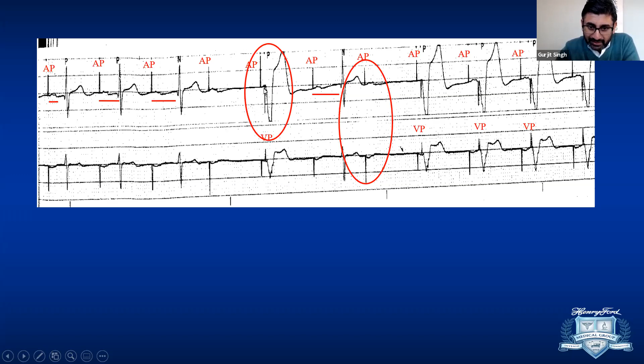Remember, we talked about last time, as Dr. Verdino also explained, this is a hallmark for a Medtronic pacemaker in MVP mode, that this ventricular pace signal comes after an AV delay of 80 milliseconds. This is different from safety pacing, which we discussed last time, which happens when you sense something on the ventricular channel at the time the atrial is pacing. That safety pacing is usually 110 milliseconds. So this is MVP working.